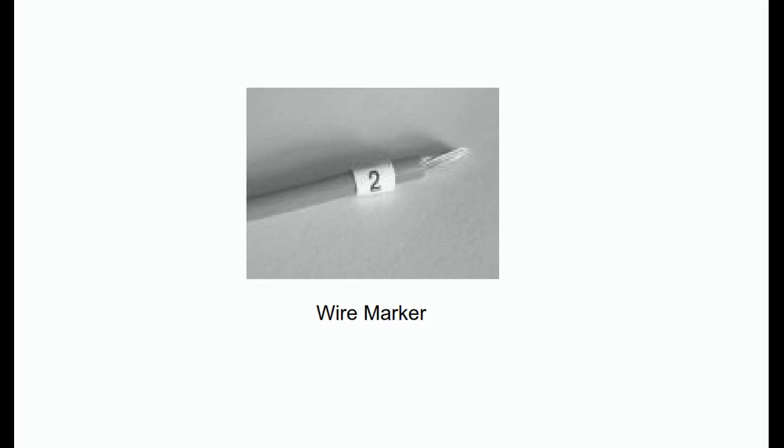Wiring: The wires are numbered. In our diagram, the left rail is wire number 2 and the right rail is wire number 1. When the system is constructed, the actual wires used to connect the components will have a label on each end, called a wire marker, as shown in figure, indicating the same wire number. This makes it easier to build, troubleshoot, and modify the circuitry.